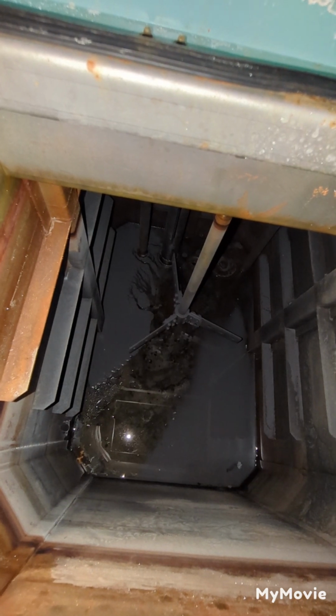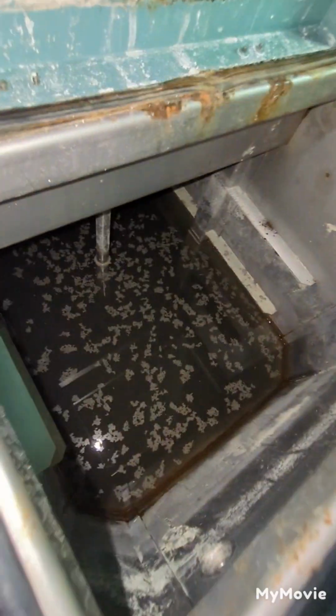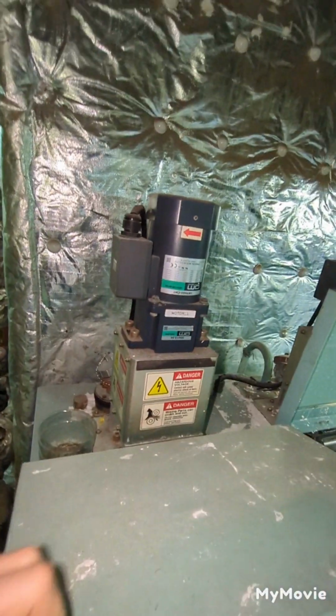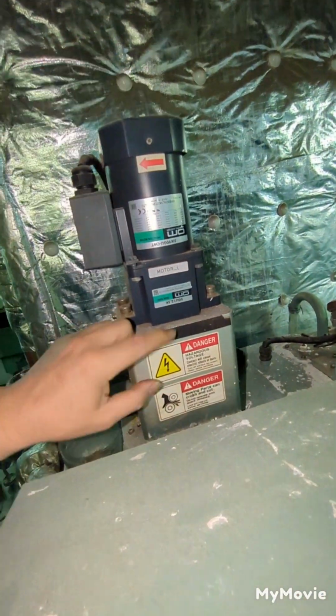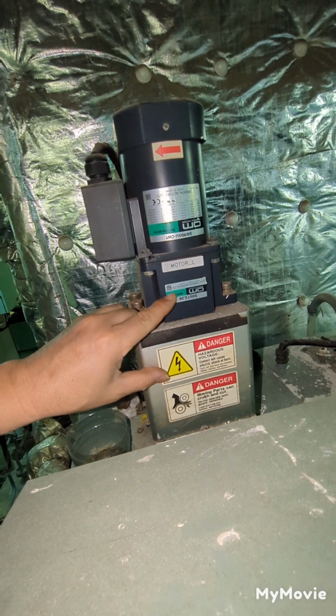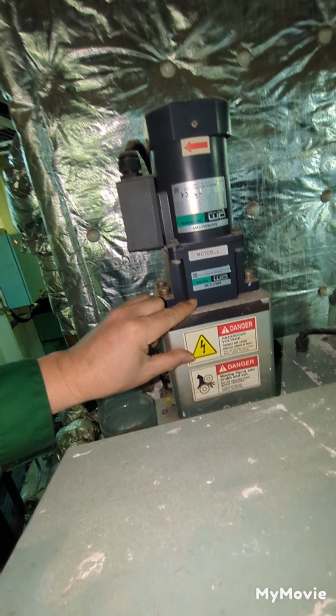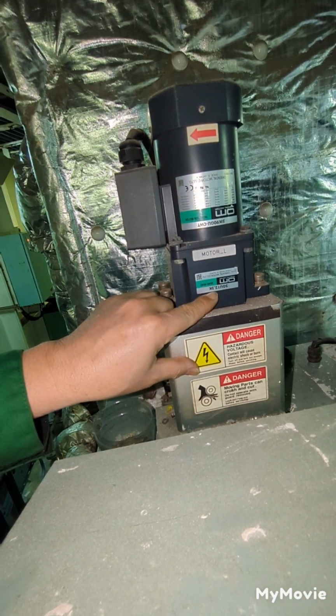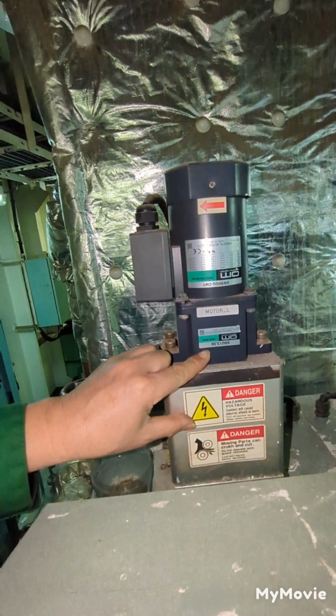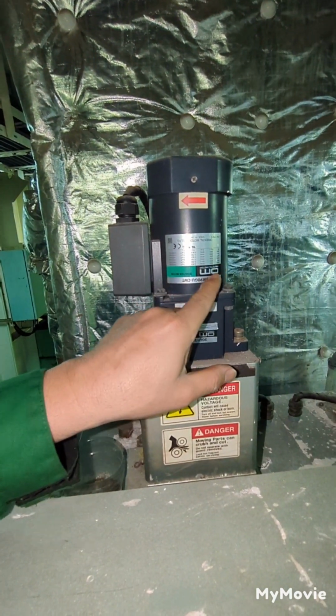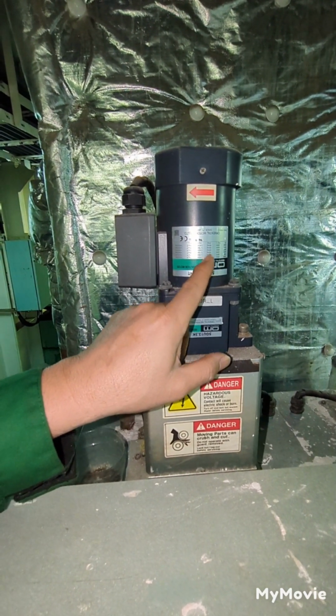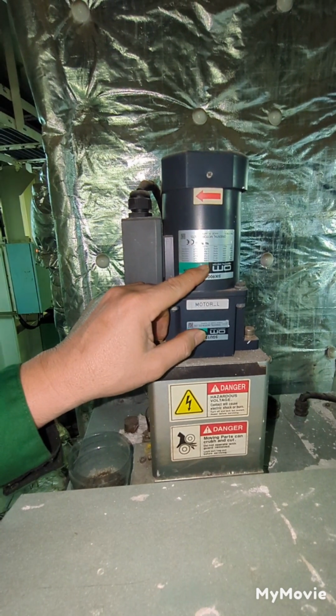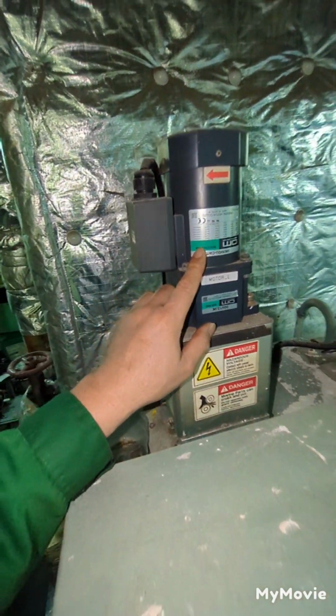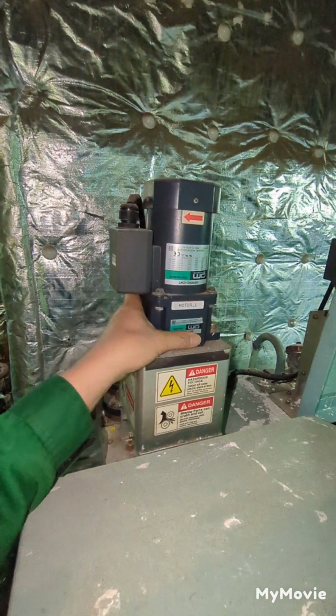This is our tank number 2, and the other side is tank number 1. As you can see, there's what's called a mixer, this is mixer motor L, made by Oriental Motor Company, made in Korea, type 5GU1 2.5K. It's 90 watts with 200 to 230 volt supply, 50-60 Hz, 0.8 to 0.81 ampere, with a capacitor of 6 microfarad inside.